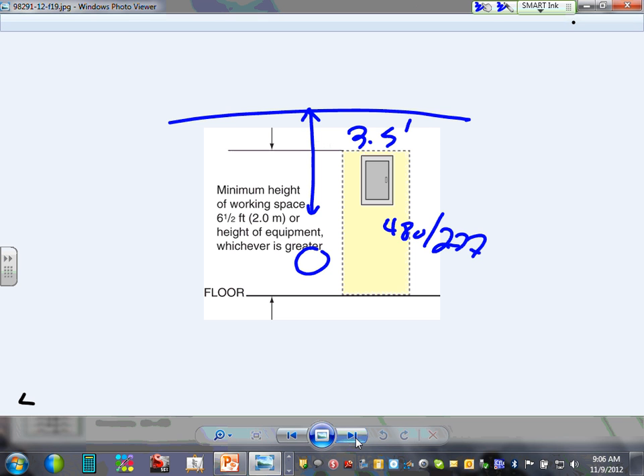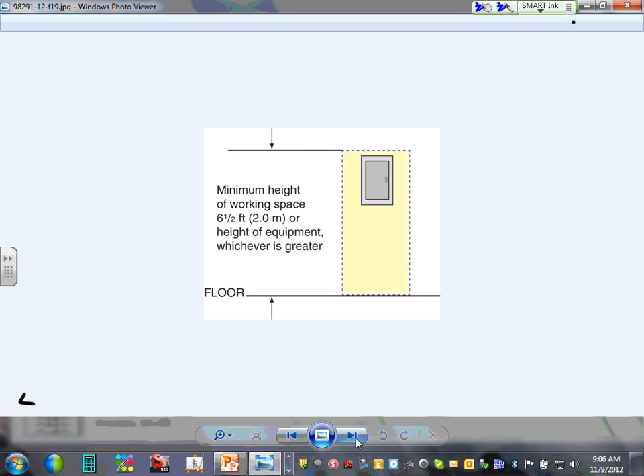The height, let's talk about the height of the working space. It's not a big deal for Chad because he's short, but for tall people, they want the height to be at least what? Can you guys see that? 6.5. So here's a switchgear right here. I'm working, I need the width of say 6 feet, because the equipment is 6 feet, 4 feet space, and a height of 6.5 for electricians to work safely around the electrical equipment. Or the height of the equipment, whichever is bigger.